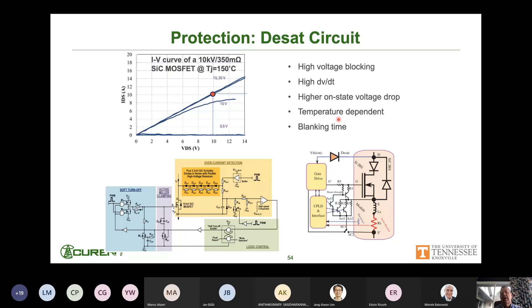Typically it needs to be temperature dependent. A lot of times we want things temperature independent, but in this case, at low temperature you want to allow higher current before taking action, and at higher temperature you want it to respond more quickly. And as I mentioned, there's also the blanking time.